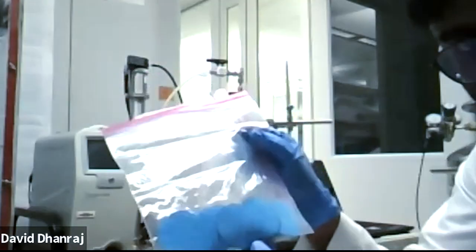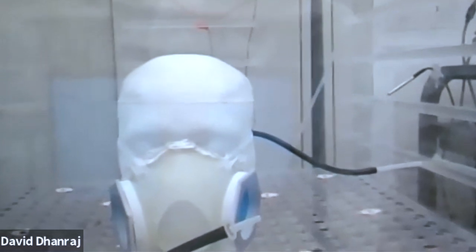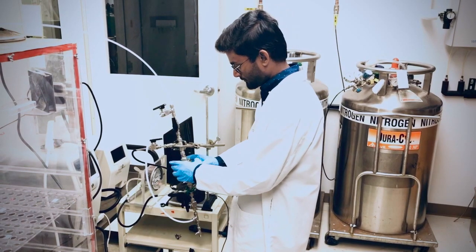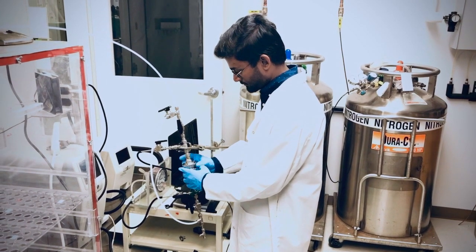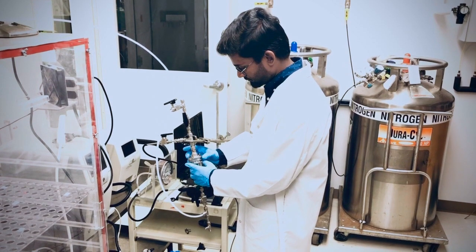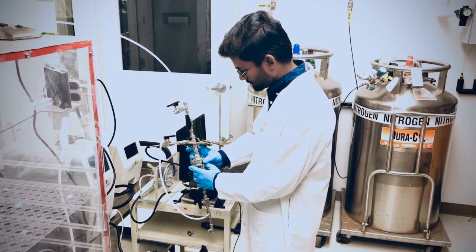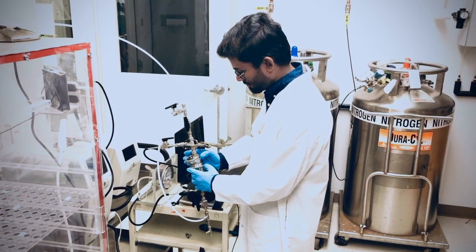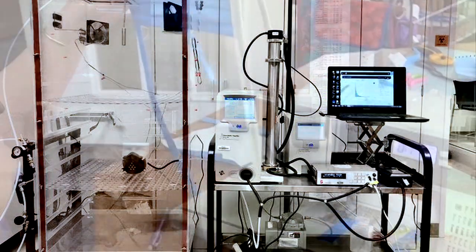Leaks alone may drop an efficiency level filtering any particle size by about 20%. Some of the ones we've tested — the hospital gown material — we put inside this filter holder and test it directly. It's a metal filter holder, and there is absolutely no leak at all while we test the fabric. But then a mask will have some leaks. The filter holder tests materials in ideal conditions, while the mannequin chamber assembly measures efficiency when made as an actual mask.